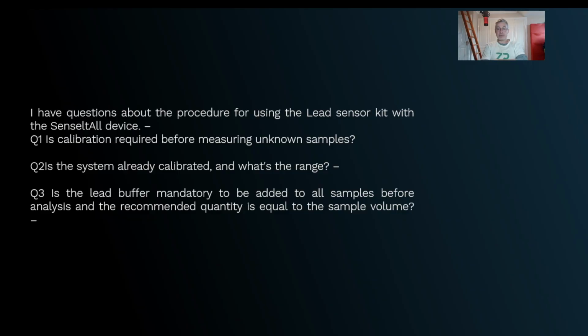The lead buffer, I would say 99% of the time, is mandatory. The only reason we've got an opportunity to not dilute, and that's in the drop-down menu, and you'll see that in a minute, is that there are some water utility companies where they've already prepared the samples and therefore we just take the sample as is. But most of the time in the real world, you've got an unknown sample, you've got the buffer. If you think the unknown sample is dilute, then it's 1:1. If you think it's a bit stronger, it's 1 plus 4. If you think it's a bit stronger, it's 1 plus 9. And if you think it's really strong, it's 1 plus 99.